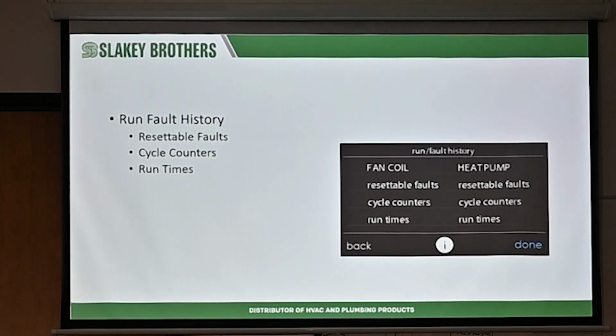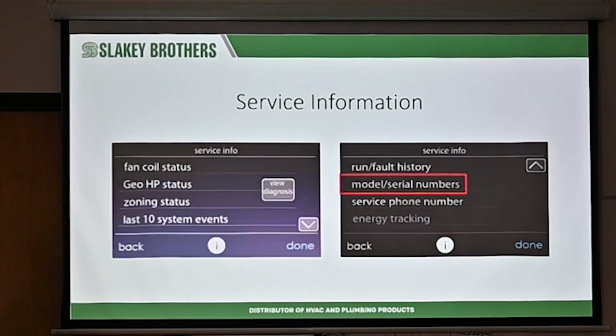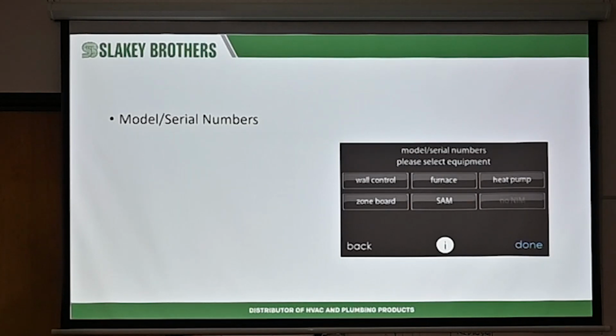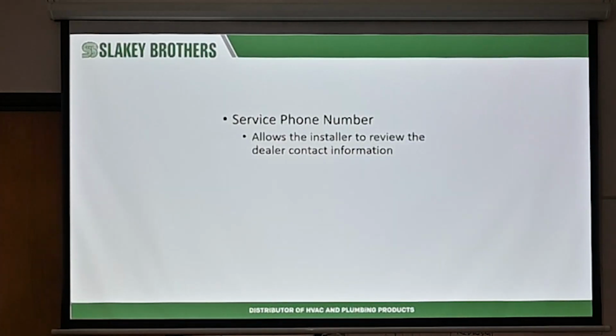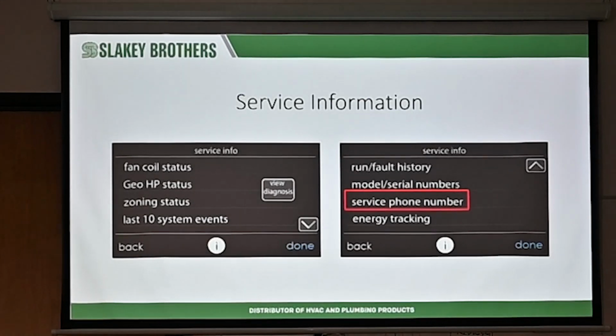Run fault history, same thing. This is what the screen looks like. You're going to be able to go into the fan coil faults, and then you can look at the resettable faults. You can reset all that stuff, whether it's a fan coil, furnace, or heat pump. And again, we just went through the model numbers, serial numbers. And if you want to have your phone number put up there, this is where you add the service phone number.